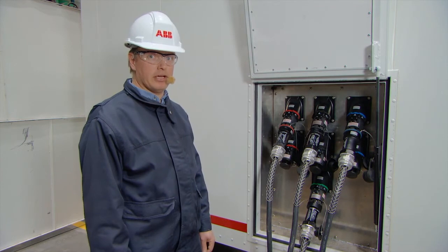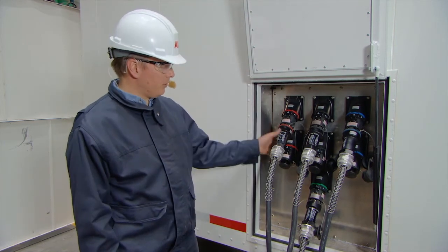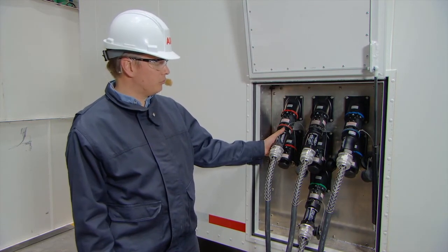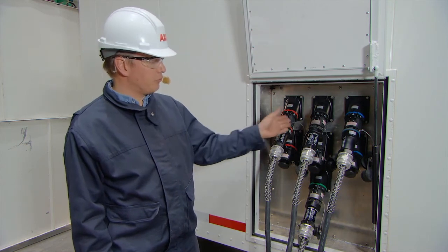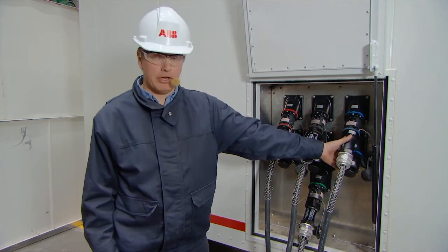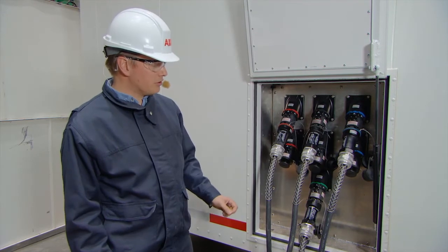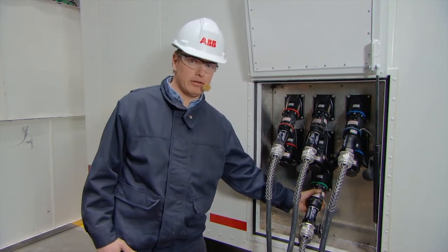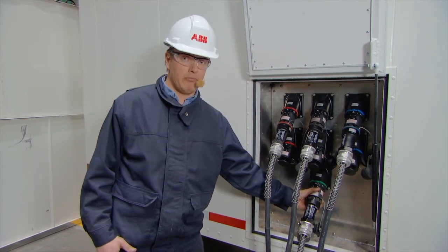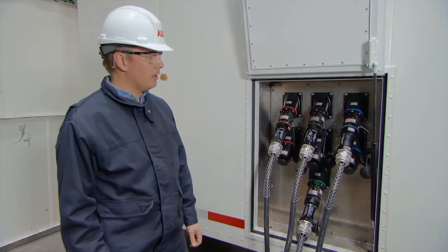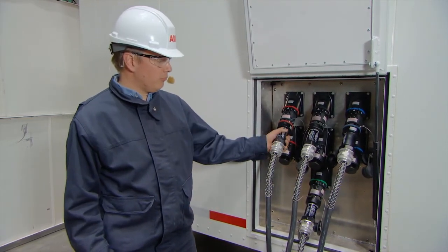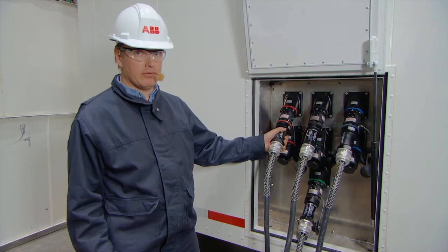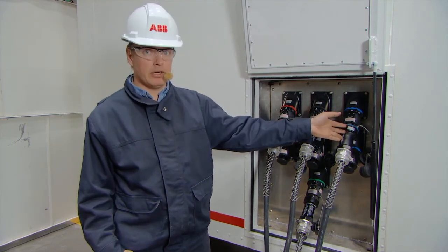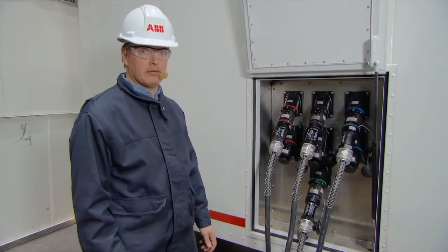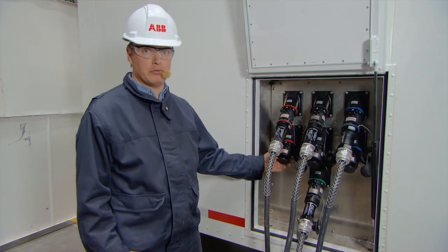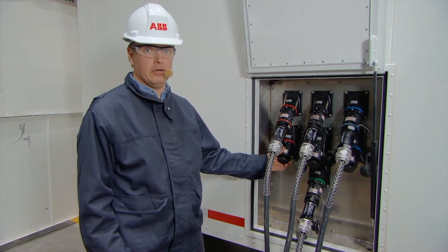This is the other side of the trailer. Here we see the power supply going from the converter to the transformer. We have 2 connections for each phase, and we have 3 phases. In addition to this, we have the grounding cable, which should connect the transformer tank to the converter via ground. Normally, for the major part of all operations, you use 1 set of cables, which gives 1 cable for each phase. The second set of cables is for when you have transformers which require more than 350 ampere of supply.